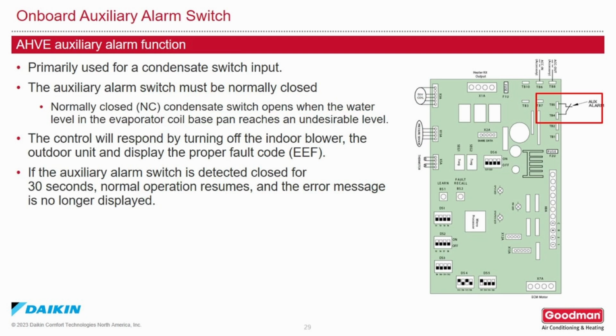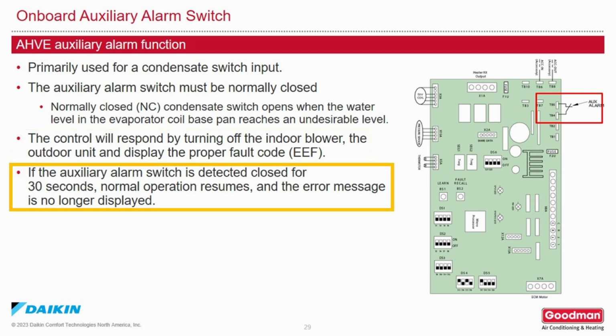The onboard auxiliary alarm switch function. Primarily this is used for condensate switch input. The auxiliary alarm switch must be normally closed. The normally closed condensate switch opens when the water level in the evaporator coil gets too high. The control will respond by turning off the indoor blower, the outdoor unit, and display the proper fault code, EEF. If the auxiliary alarm switch is detected closed for 30 seconds, normal operation resumes and the error message is no longer displayed. Heater kits.